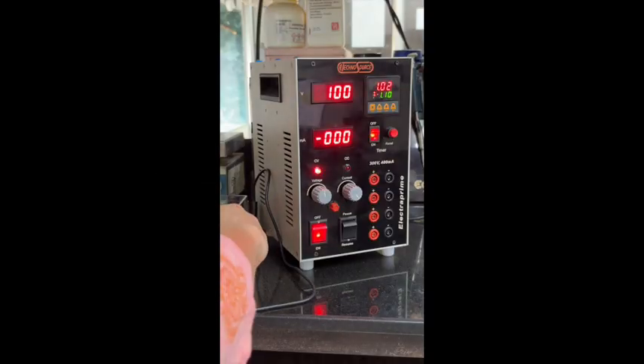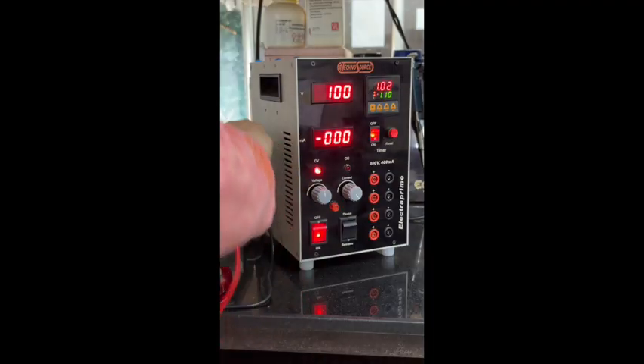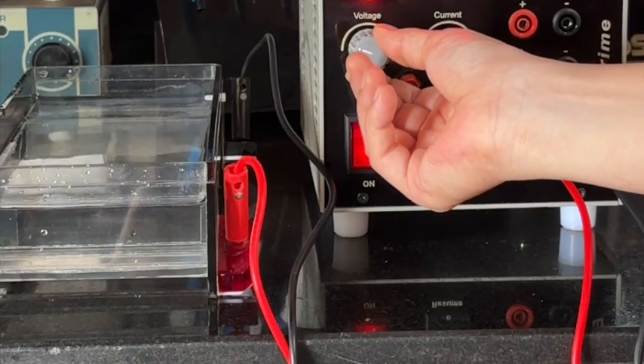Cause number 8. A defective control circuit or transformer issue. Disconnect any apparatus if connected to the power supply. Check if voltage can be set over the full range. If OK, then connect the load and rotate the current knob slowly clockwise.